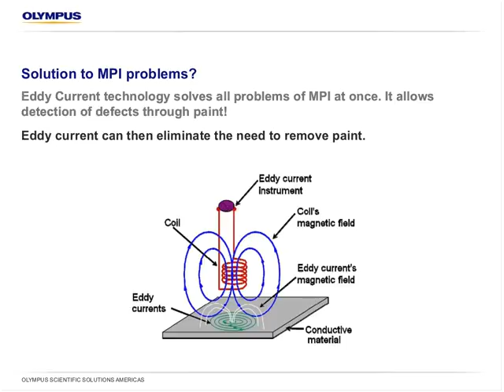That favorizes or helps spreading eddy current across the industry as a replacement to MPI. So Olympus just released last year a new eddy current flaw detector called the NORTEC 600. That's the instrument we're proposing for this improved weld inspection method. It's pretty much the only instrument on the market that bears the ISO 15548 standard, or EN 15548.